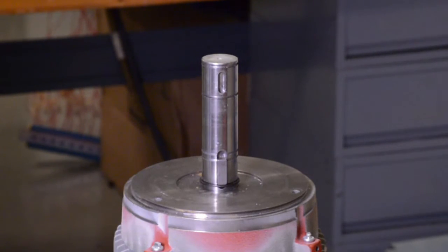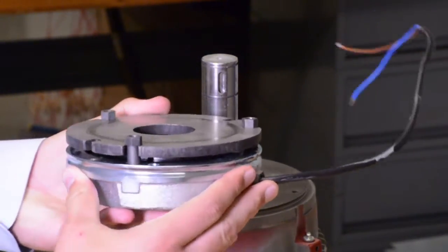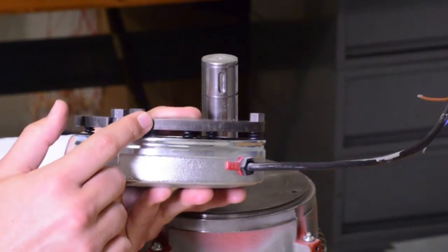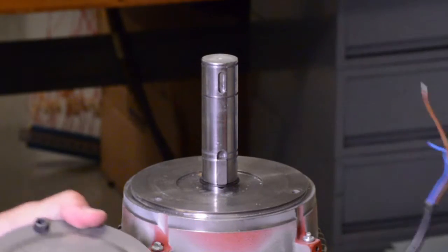Second, ensure the shaft is centered with the mounting holes. Third, ensure there are no obstructions in the air gap, which is between the magnet and the armature. The brake assembly is done with no power being supplied to the brake.